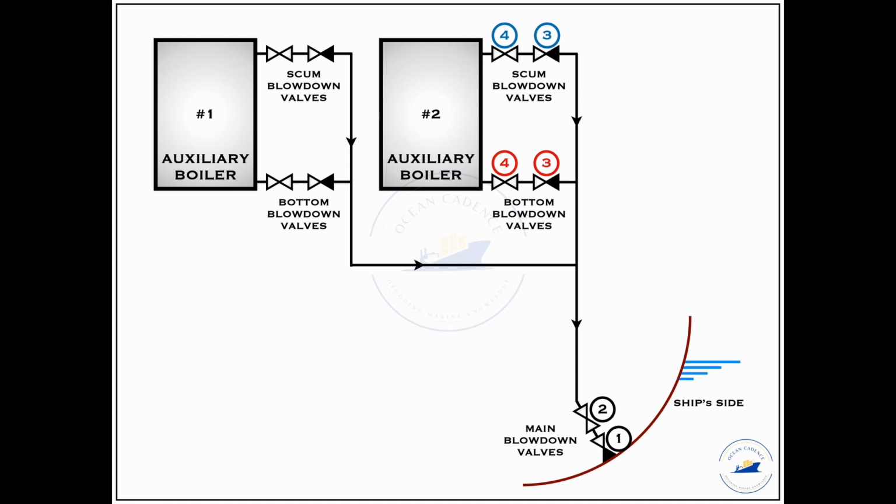Once the blowdown process is carried out sufficiently well, we have to make sure that all the valves are again isolated and the ship side valves are locked, so that if any external authority comes on board at restricted ports, let's say the US where NPDES is under prosecution, we can show that no discharge is occurring at the port under any condition. By locking the valves on the ship side, we ensure that the key is always with the chief engineer and the valves are locked down. So it also gives a surety that no blowdown is carried out at ports.